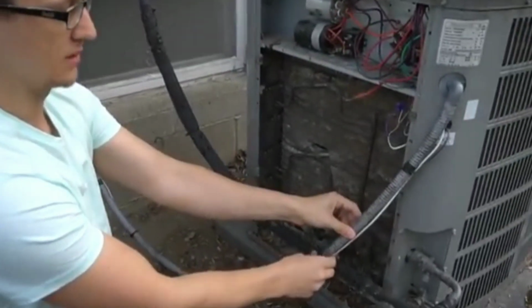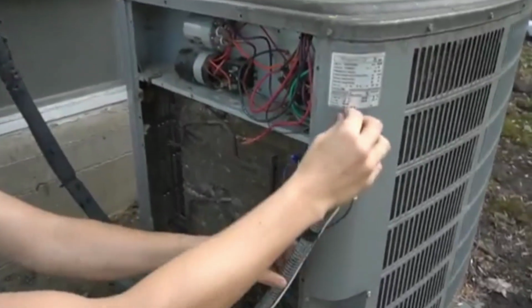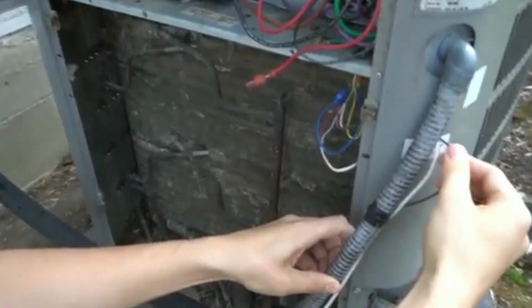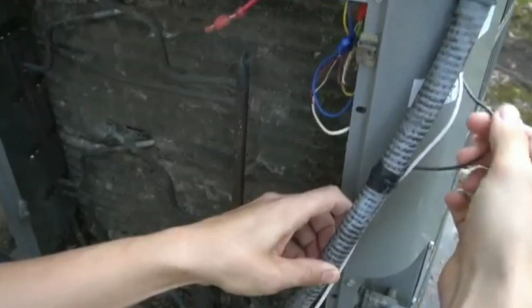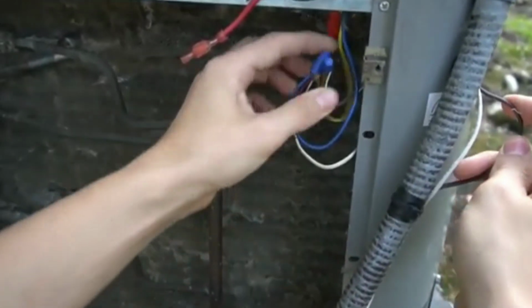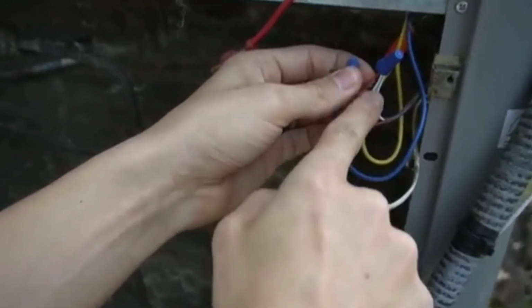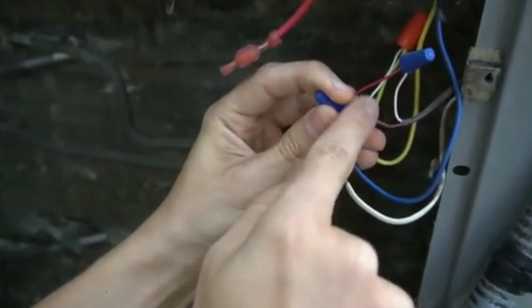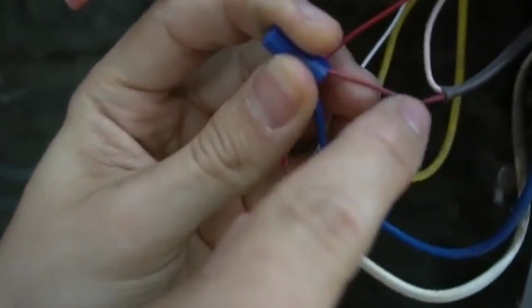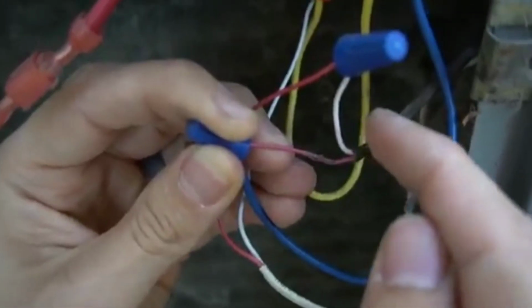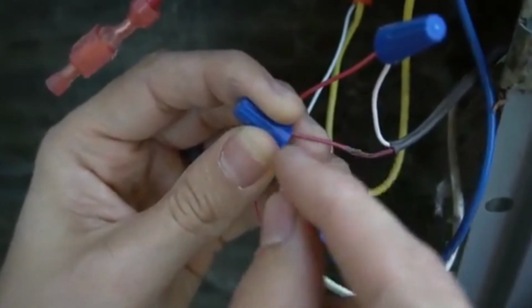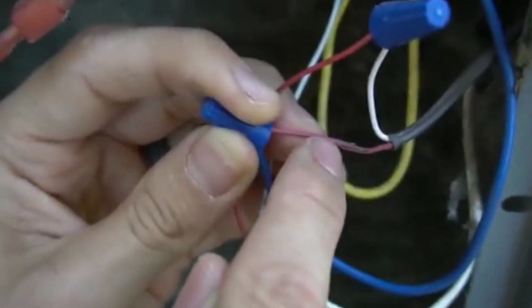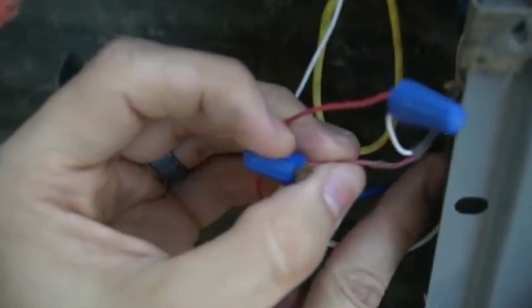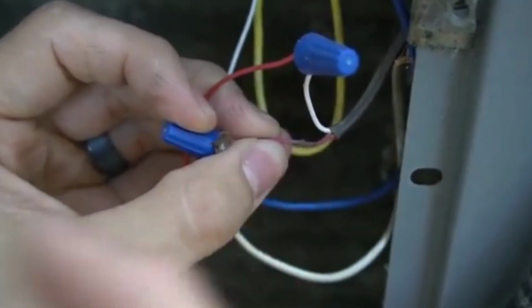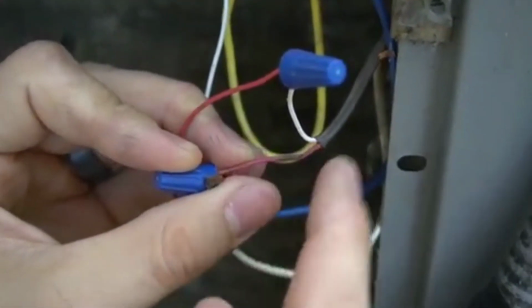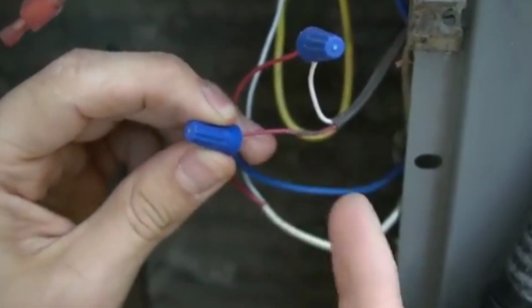Also, along with the electrical whip, if you look here, usually it'll be right by the whip going in from the 240 volts. You'll also have 24 volts coming in from the house, which will typically be a brown wire like this, which has 2 more wires inside of it, a white and a red. If you can see right here, I don't know how visible that is in the camera. See how that wire has a bare piece right there? I should actually snip this wire right here, strip it down, and then rewire nut these wires so I don't have that bare spot. Because if this bare spot right here touches anything metal, it'll short out and blow a fuse on my control board in the furnace. So this is the kind of stuff you're looking for when you're looking at these wires. For bare wires or broken connectors.